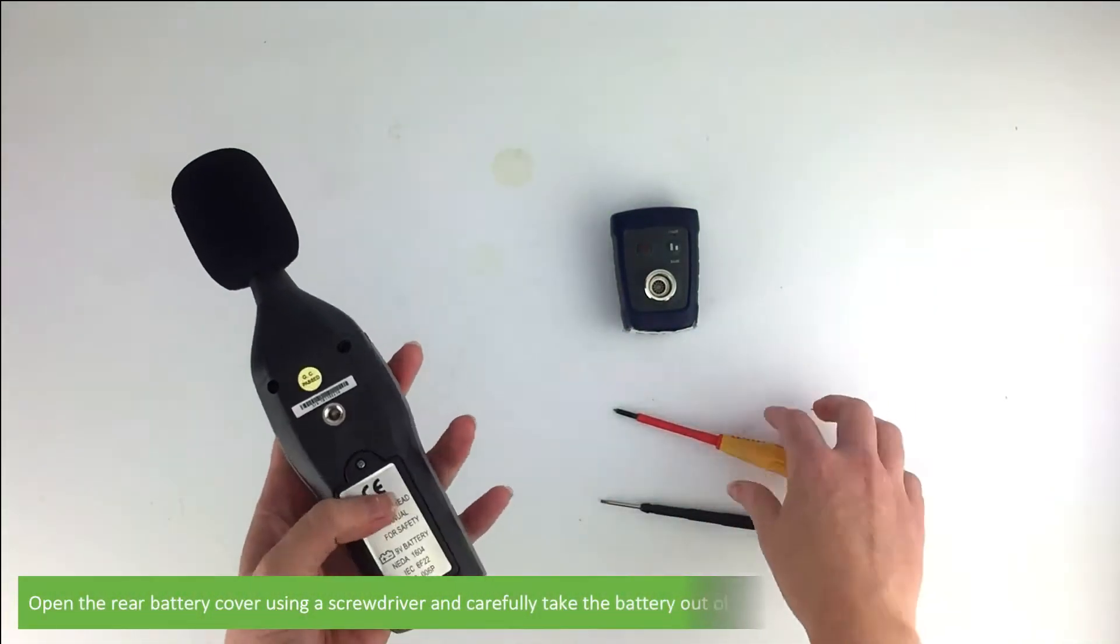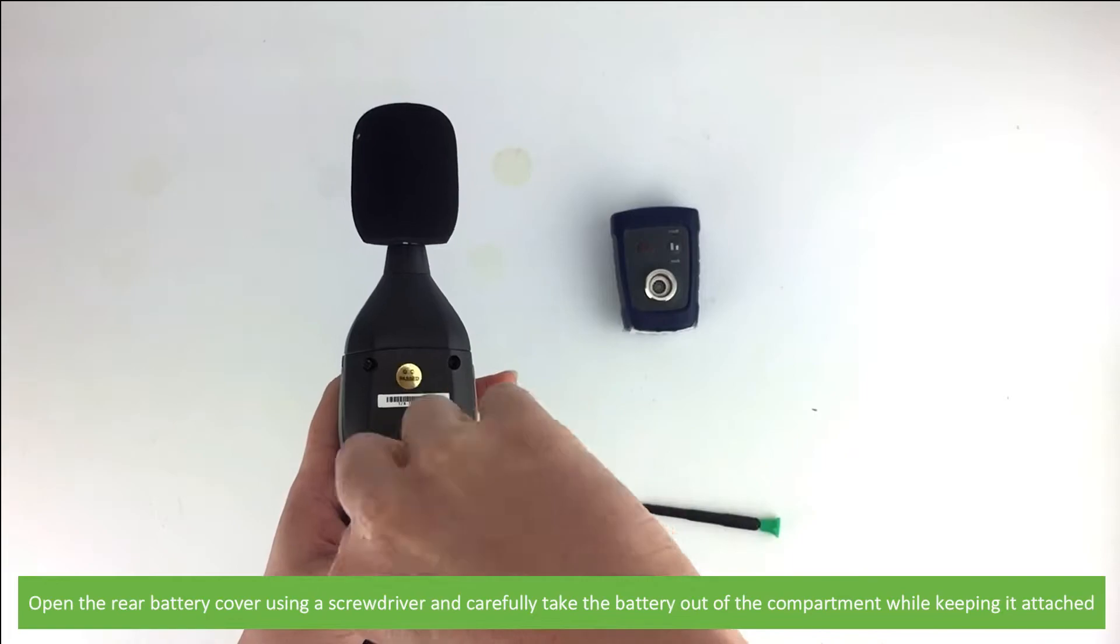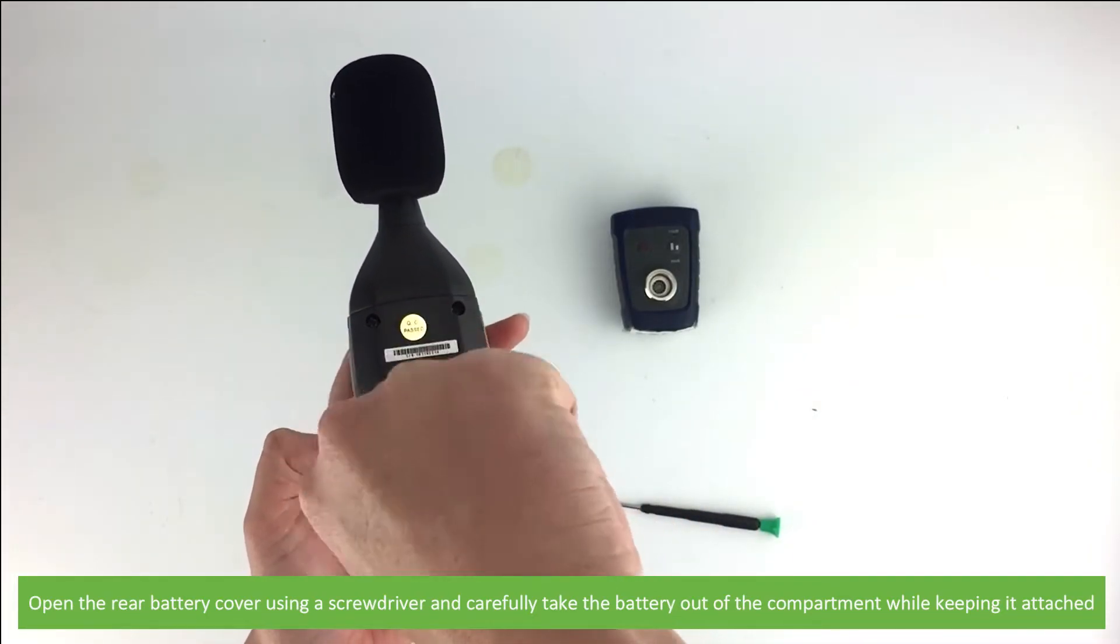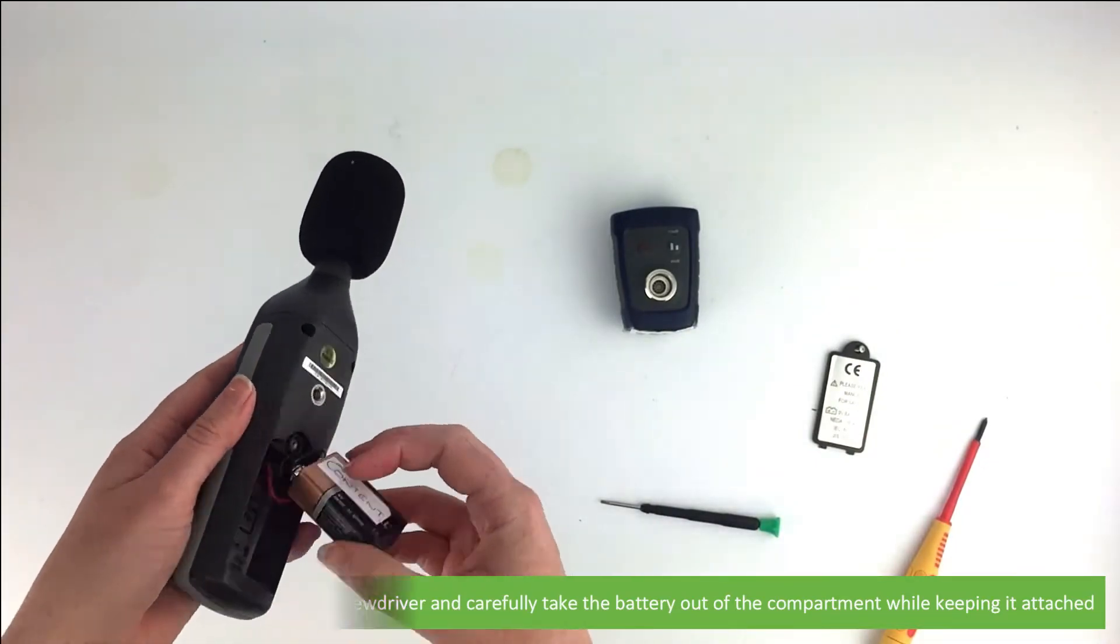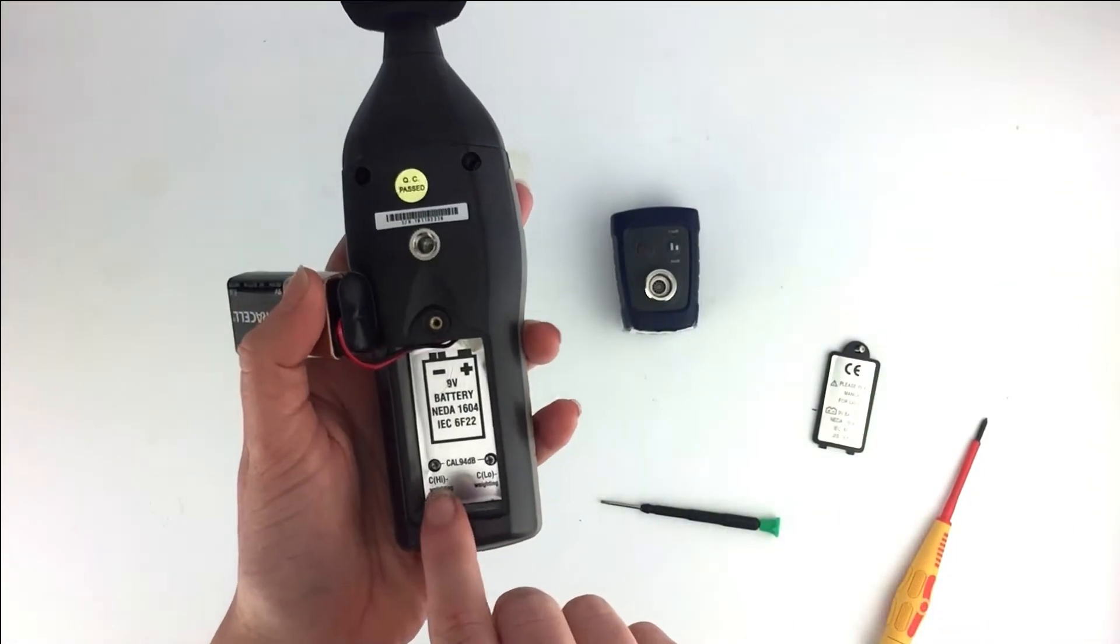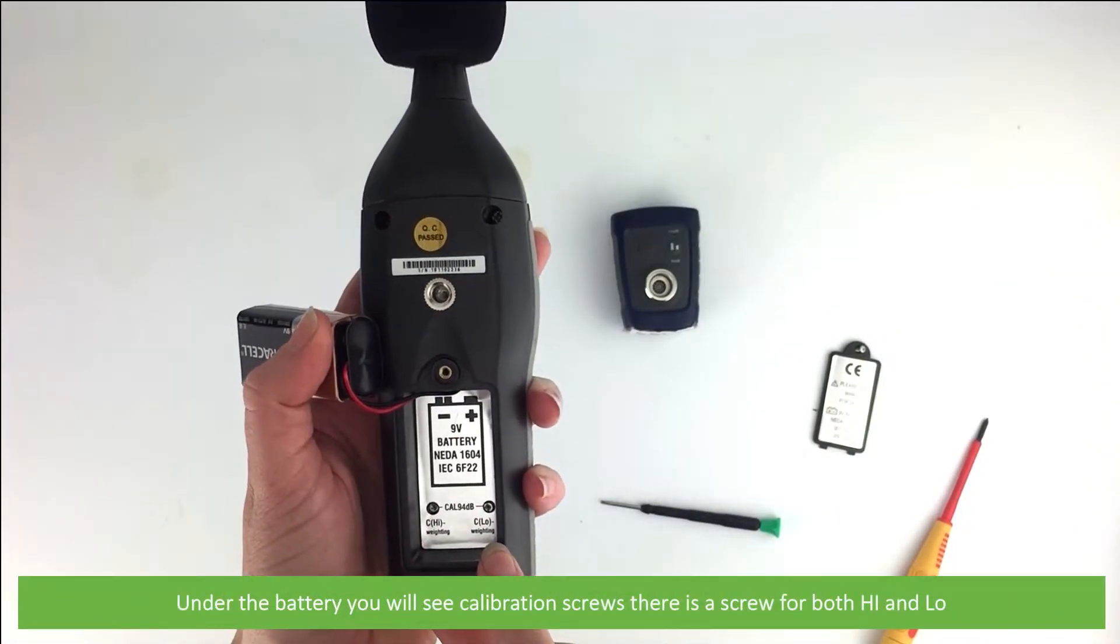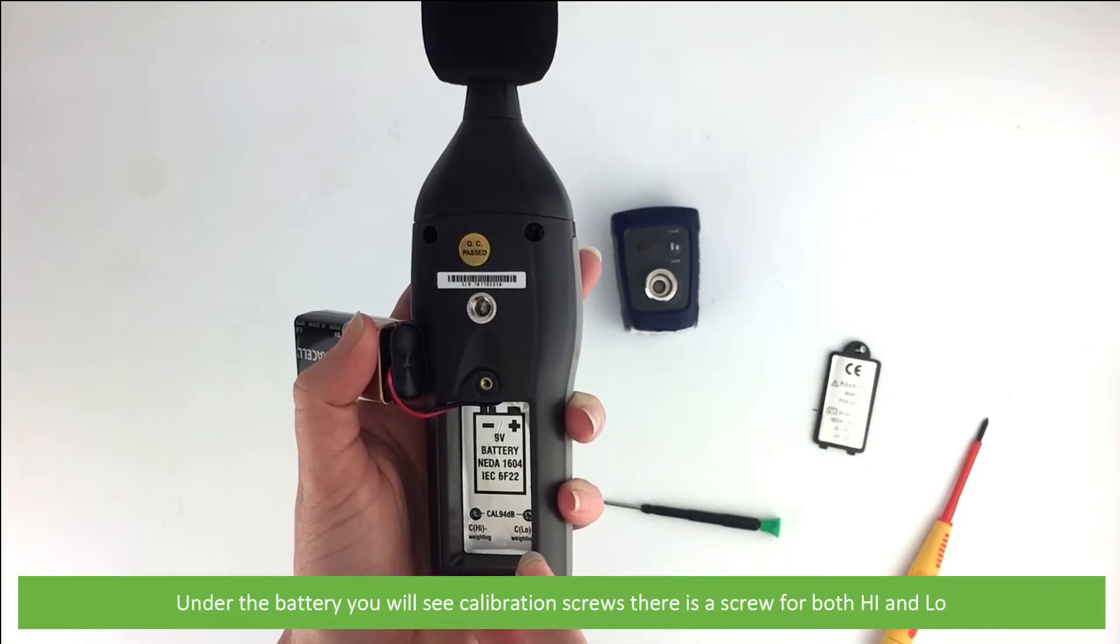Then open the rear battery cover using a screwdriver and carefully take the battery out of the compartment while keeping it attached. Under the battery you'll see calibration screws. There is a screw for high and a screw for low.